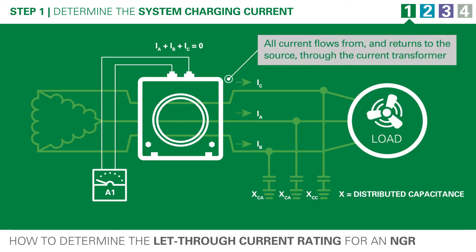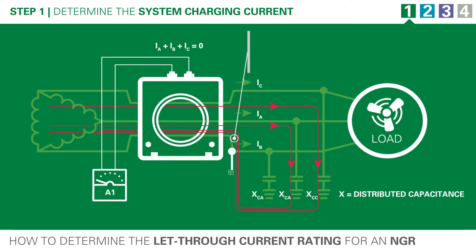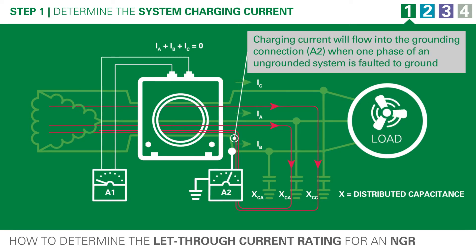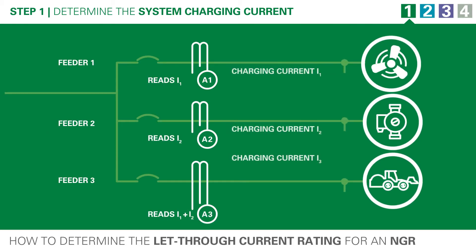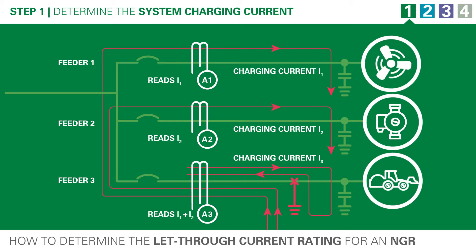This capacitance is distributed through the system and is what references an ungrounded transformer or generator to ground. When a ground fault occurs on this ungrounded system, the voltage on the remaining phases rises and the fault current flowing through the ground fault is the charging current. When we consider a ground fault on a system with multiple feeders, a ground fault relay on an unfaulted feeder will read that feeder's charging current, and a ground fault relay on the faulted feeder will read the sum of all the charging currents from the unfaulted feeders.